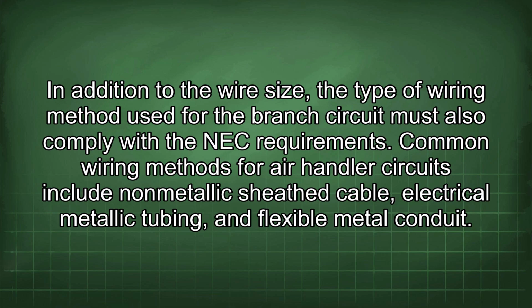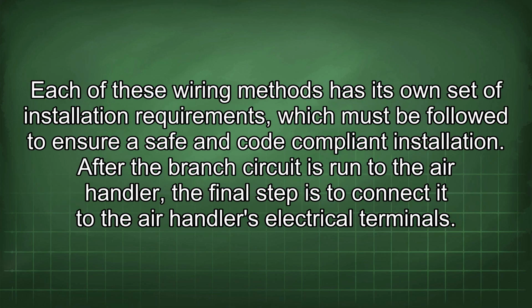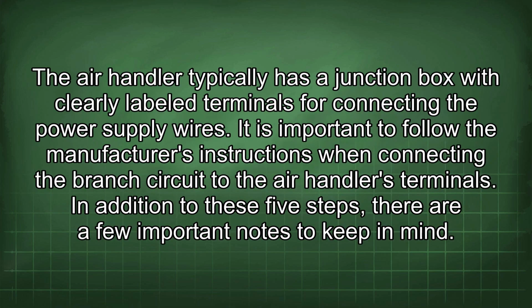In addition to the wire size, the type of wiring method used for the branch circuit must also comply with the NEC requirements. Common wiring methods for air handler circuits include non-metallic sheathed cable, electrical metallic tubing, and flexible metal conduit. Each of these wiring methods has its own set of installation requirements, which must be followed to ensure safe and code-compliant installation. After the branch circuit is run to the air handler, the final step is to connect it to the air handler's electrical terminals. The air handler typically has a junction box with clearly labeled terminals for connecting the power supply wires. It is important to follow the manufacturer's instructions when connecting the branch circuit to the air handler's terminals.